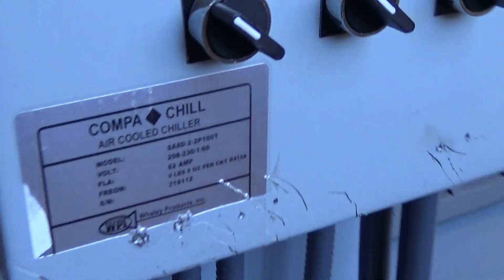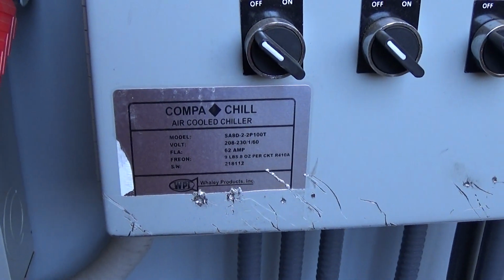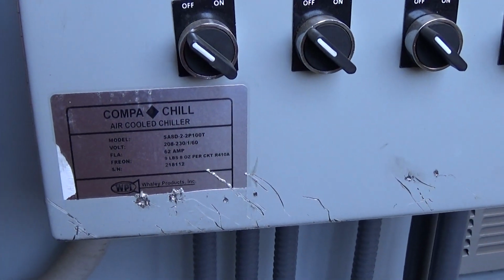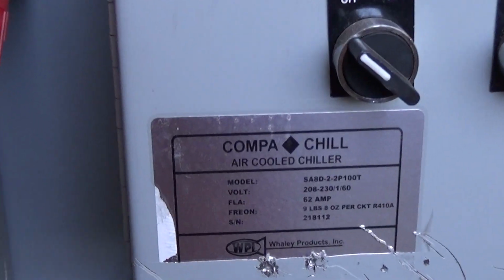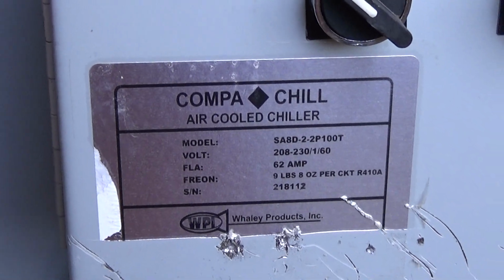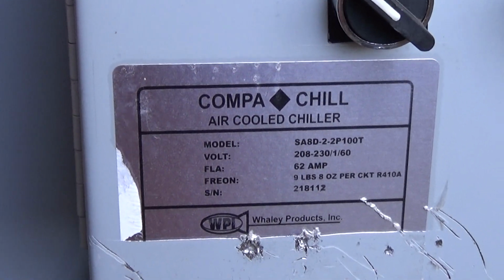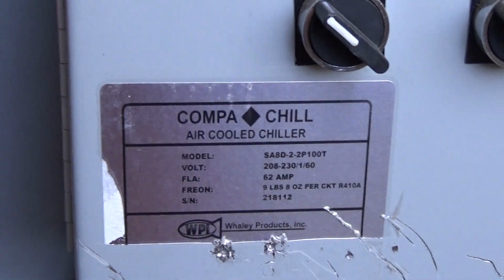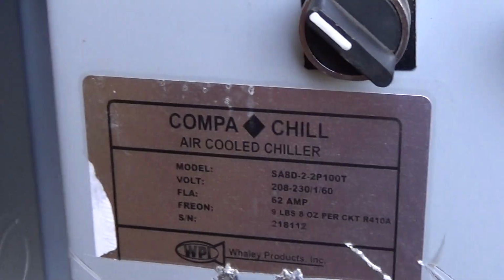there's not a fused disconnect, but there is a disconnect that's included right here, which is kind of nice. The unit says 62 full load amps, and that's about right. I think when both, we're looking at the ratings of each compressor and both pumps and the fans. If this thing's running flat out on a warm August day, it's going to be drawing pretty close to that.